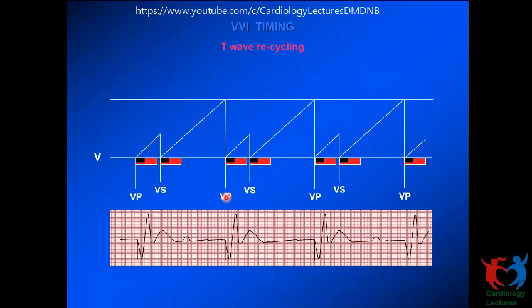So in this case, if you do not have a programmer on hand to identify it's a T-wave oversensing, and if you're sitting in the OPD and you only have the ECG, then look at where it delivered a V pace and work your time backwards if you know the lower rate, and if it ends exactly on the T-wave beat after beat without even a programmer, you know that it is a T-wave oversensing. So there are two ways that you can overcome this. You can reduce sensitivity, provided your R wave is good enough to allow you to do that. If not, you can increase the refractory period. That also has a little bit of a problem. If you program a high lower rate, then if you increase the refractory period, competitive pacing can happen. So these are the two ways you can manage that.